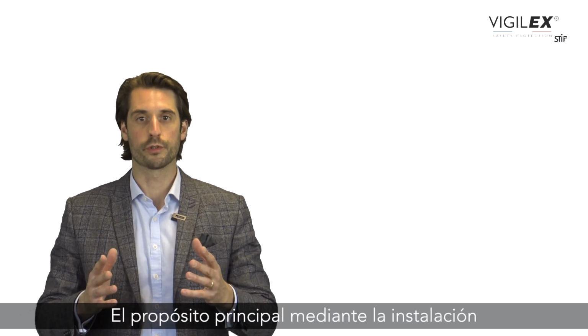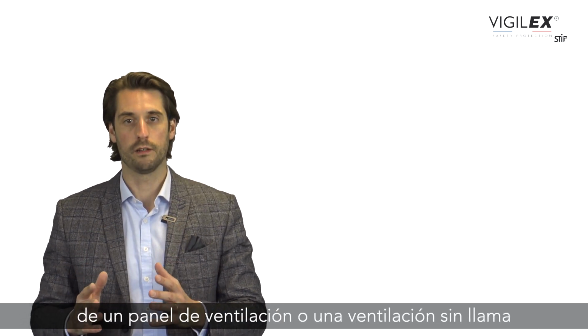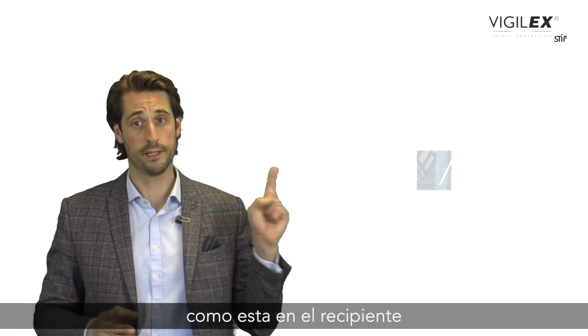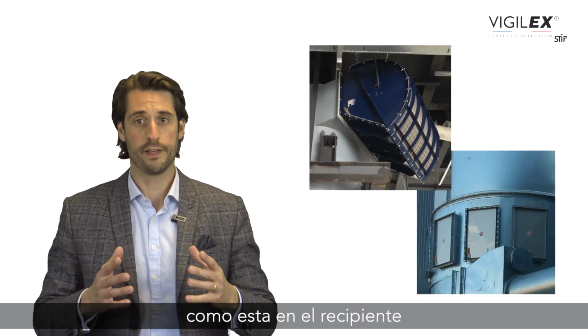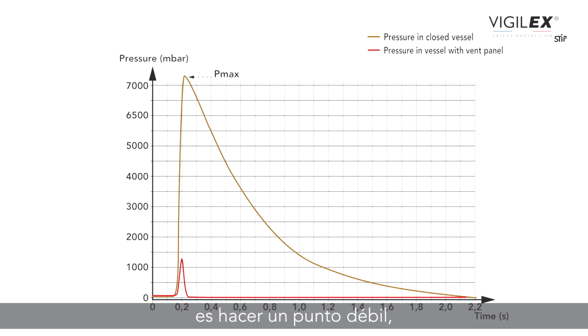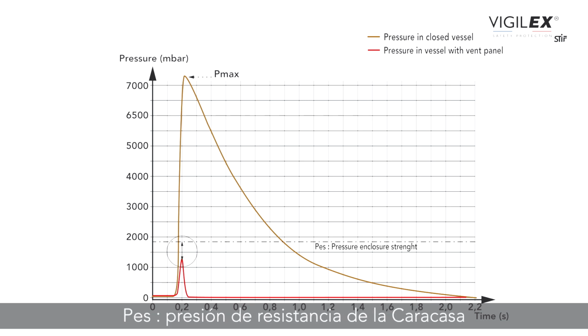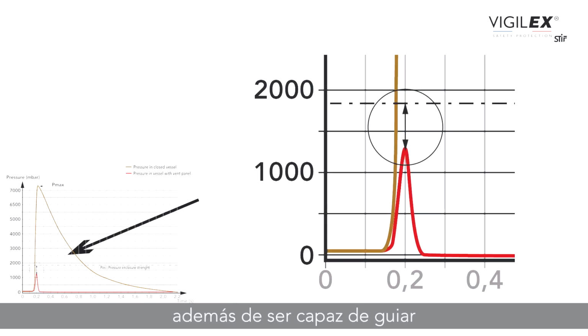The main purpose of installing a venting panel or a flameless venting, like this, on a vessel is to make a weak point in order to relieve the pressure before it reaches the maximum strength of the vessel, called PES, pressure enclosure strength, in addition to being able to guide the pressure in a safe direction.